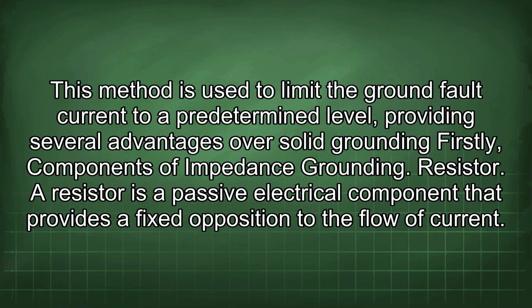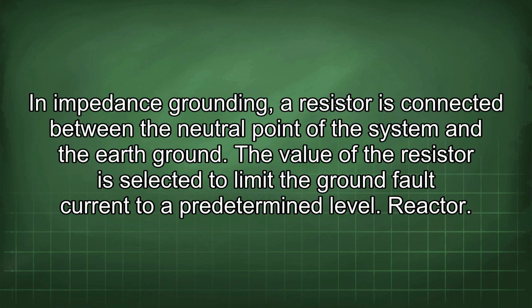Firstly, components of impedance grounding. Resistor. A resistor is a passive electrical component that provides a fixed opposition to the flow of current. In impedance grounding, a resistor is connected between the neutral point of the system and the earth ground. The value of the resistor is selected to limit the ground fault current to a predetermined level.